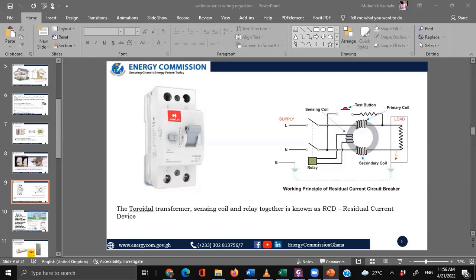But we are saying there should be some tolerance, a minus or plus. So the RCD is weighing these options. Okay, fine, 5 is coming, but about 4.99 or 4.98 is coming back, or even exactly 5. So when it deviates over the rated capacity of this RCD, let's say 5 is coming from the live, and 3 is coming back through the neutral. That means 2 amps is missing. Where is it? This is where it becomes critical. That 2 amps might be hovering around an appliance, or it might be going to the ground, or it might be passing through a human body.